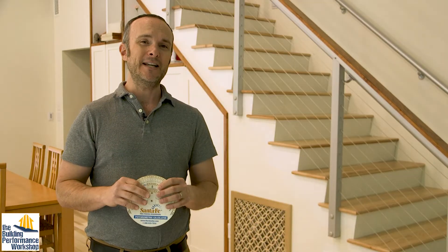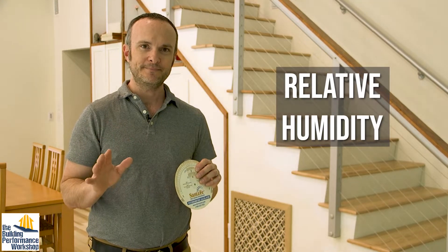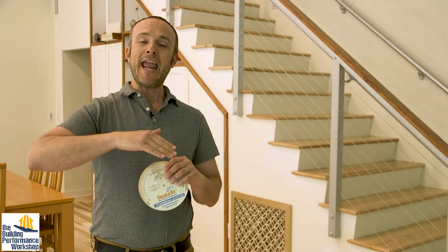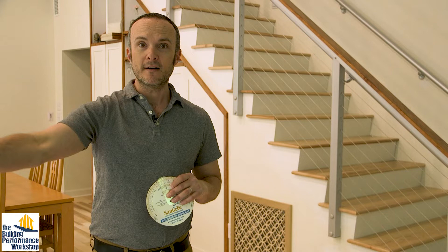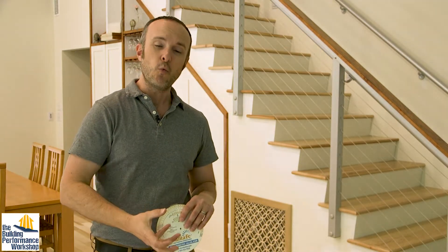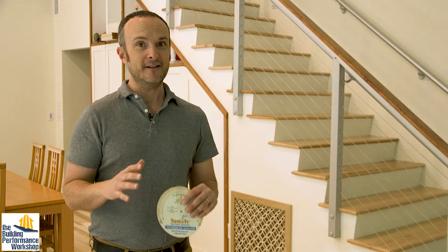The humidity metric you're going to hear most of the time — whether listening to the weather or talking about indoor spaces — is relative humidity. What's relative about it is the temperature. Air at different temperatures holds different capacities of water. Air at 96 degrees can hold a lot of water; air at 32 degrees does not hold very much at all. So even if it's snowing outside and you bring that air inside at 100% relative humidity and warm it up to 70 degrees, it's going to be super dry — which is why you'll have a big problem in a place like the Yukon.